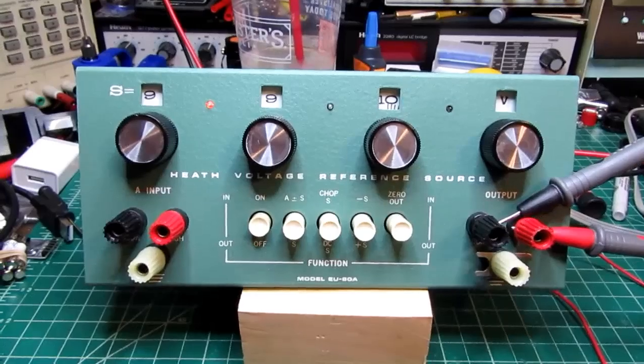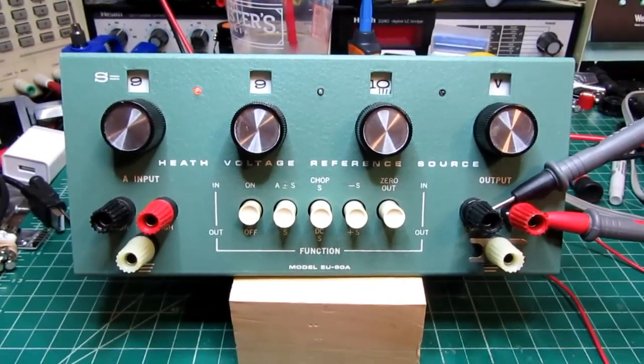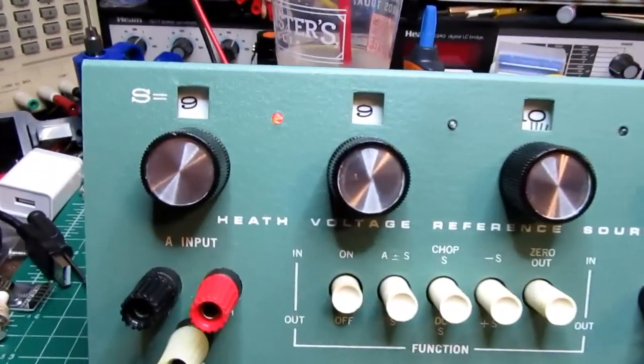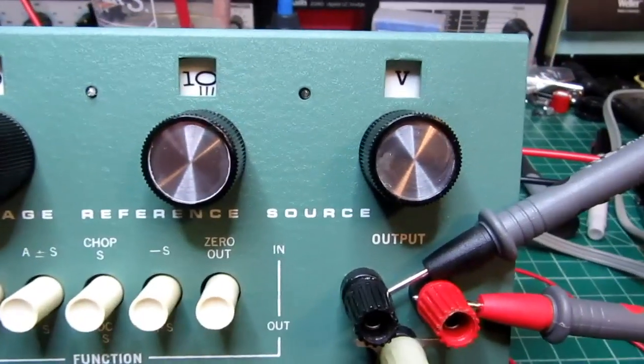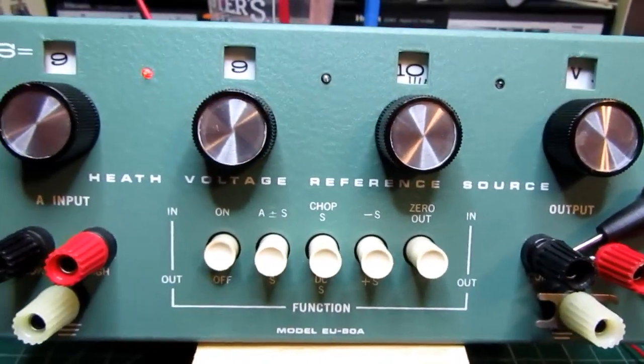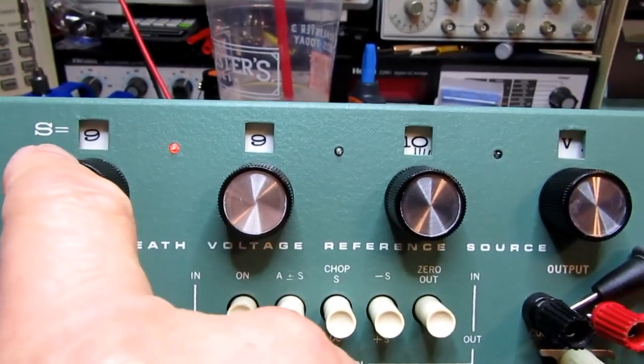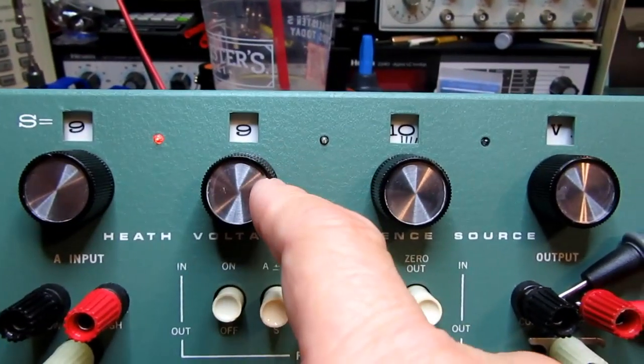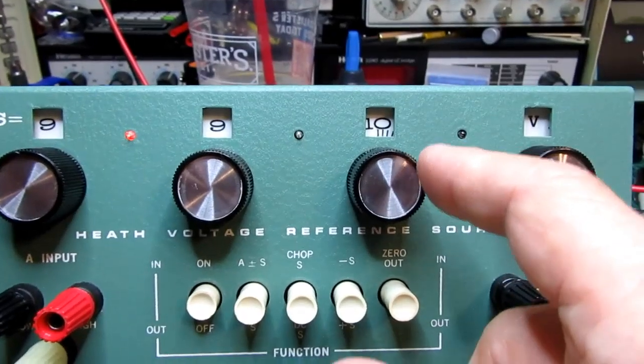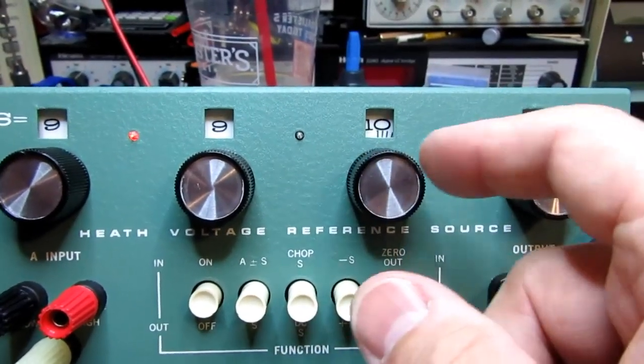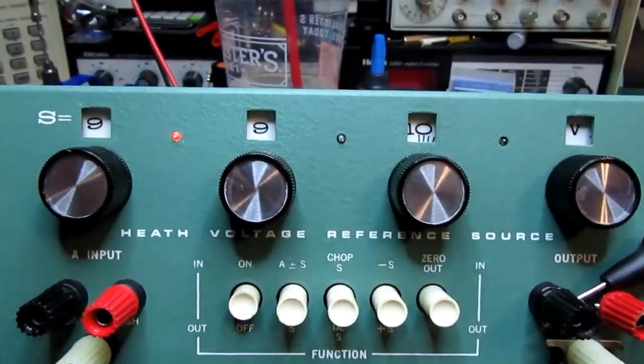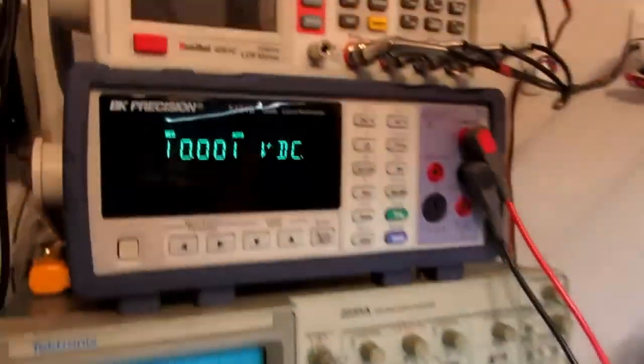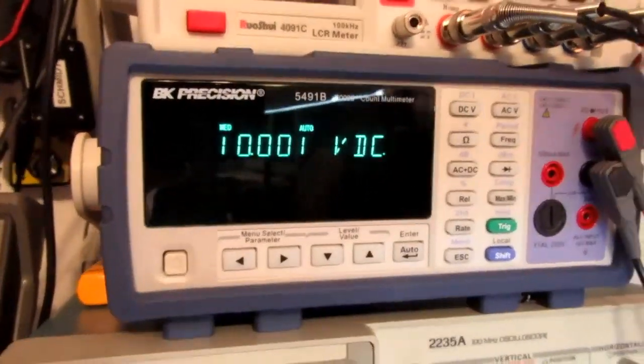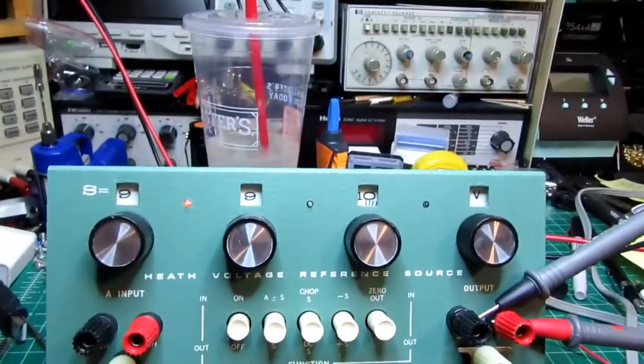Alright, let's just do the quick demo. I've double checked the calibration again. I'm set to 9, 9, 10 on volts, so that should be giving me 10 volts. So it's 9.9 and then 10 from that position. It adds up, so it rolls over to 10 volts. And I'm getting 10.01 volts on the meter, which is about as close as I could hope to get.